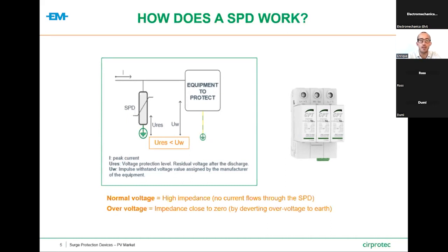The key here is to be sure the SPD selected is the proper one to protect our installation, is to assure that the residual voltage the SPD is letting through to the equipment to protect after the discharge is below the maximum voltage the equipment to be protected is able to withstand.